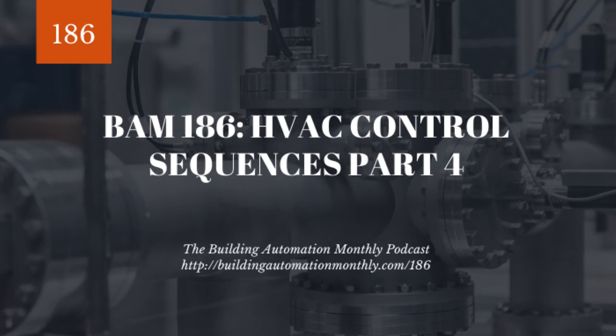I've seen this happen. This is kind of the inverse of if you had fire isolation dampers downstream from a fan, and those were closed, and that supply fan was blowing air, and that air had nowhere to go, so it would pop the ductwork. Well, this would suck in the ductwork. So we need to be cognizant of that. Our outdoor air dampers are open upon our fan signal to start. And if the fan doesn't start, then the dampers are going to close, and we're going to have a fan failure alarm. But if we don't get damper status, then we are going to actually go and turn off the fan, because that is one of our biggest issues.